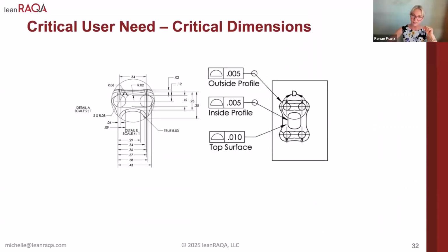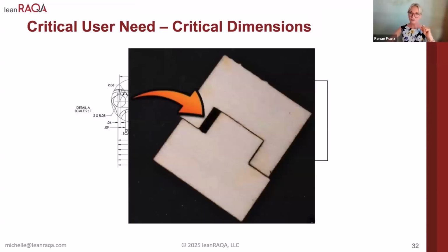Well, we had an instance going back to that radio frequency sealer. We had a critical dimension that we didn't even know we had. When the jaws of the sealer come together with the radio frequency energy, if there's any sort of gap, that radio frequency energy will spark. So what happened? We sent sealers to the cord blood bank in Singapore, and they lost 10 units of cord blood because we had a critical dimension that we did not know about, and it was off.